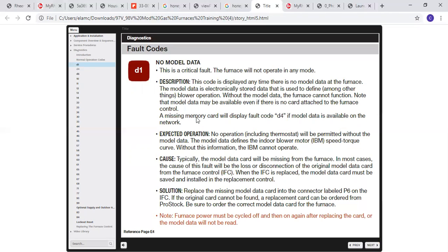And some of the fault codes we see here, I won't go through every single one, but I'll hit some high points. A D1 indicates there's no model data. So possibly your model data card is loose or corrupted or damaged in some fashion. If you don't have model data, it doesn't know really what's going on. So you can expect no operation with a corrupted or missing model data card. The solution is to replace the missing model data card.